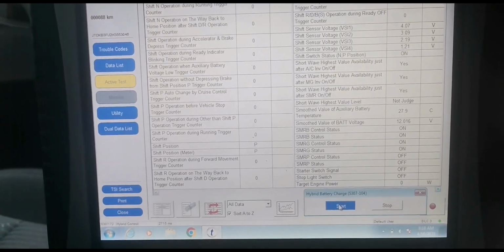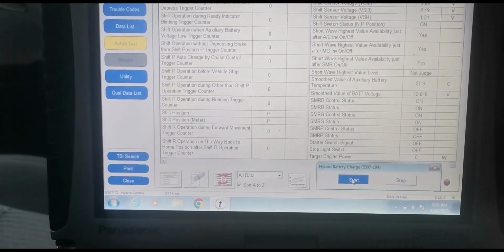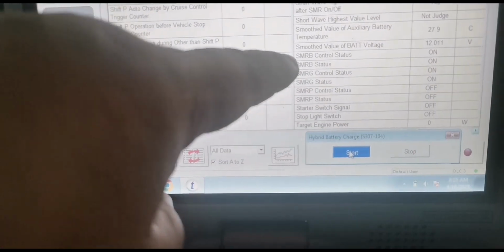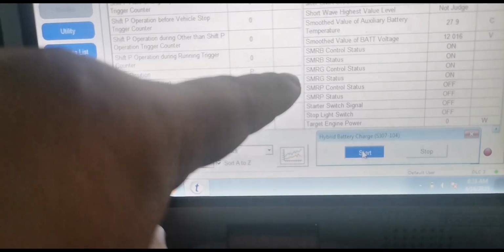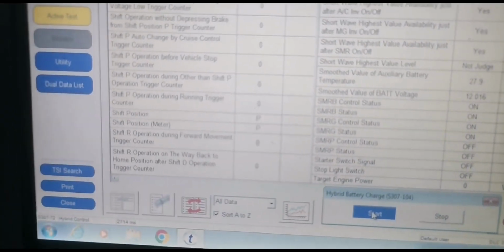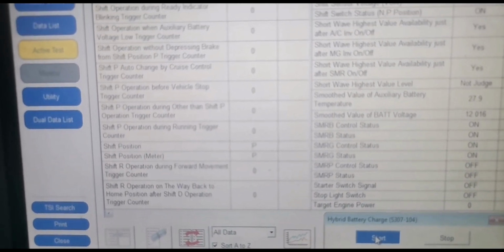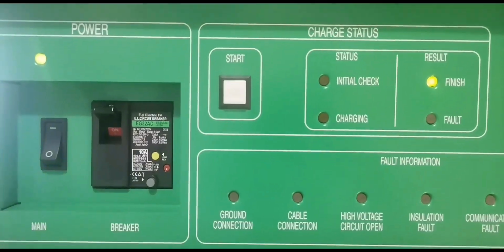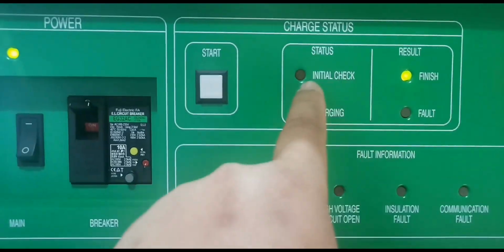Now we are on our third cycle. Same thing: do the active test and make sure the system main relay positive, pre-charge main relay, and ground main relay are switched on. Now we will go to the charger again, switch on for the last time for the third cycle. Okay, third cycle is finished.